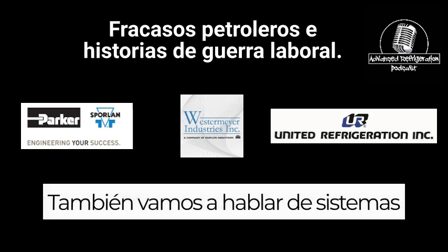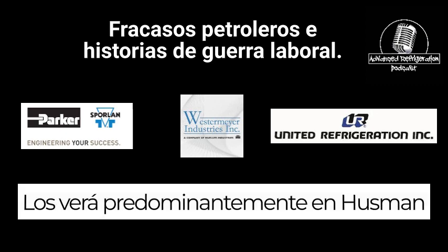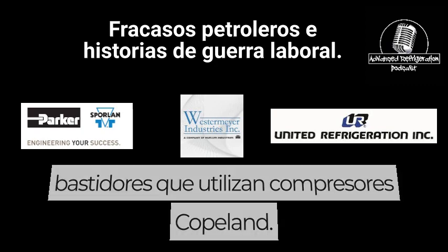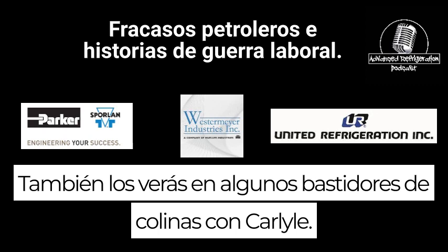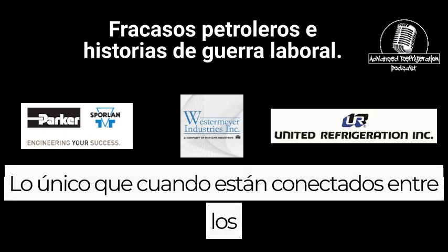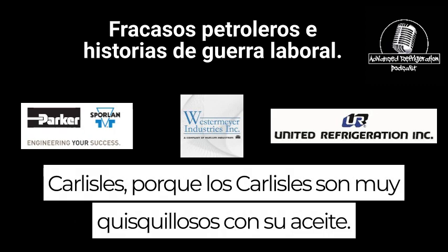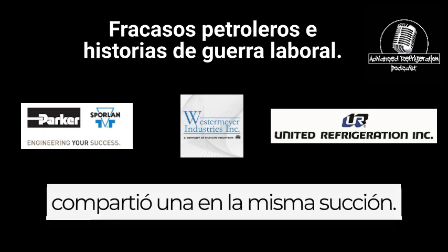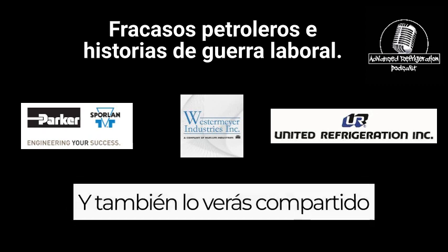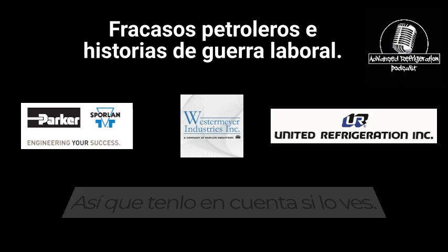All right. We're also going to talk about systems that have oil equalization lines. You see these predominantly on Hussmann racks that are utilizing Copeland compressors. You'll also see them on some Hill racks with Carlyle. With the Carlyles, because they are very finicky with their oil level, you'll only see the oil equalization line shared on the same suction, and you'll also see it shared on compressors of similar heights. So be mindful of that.